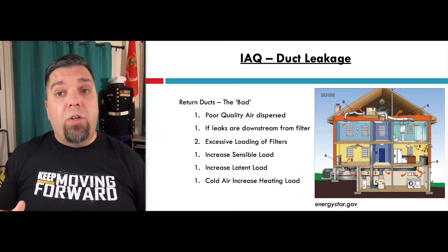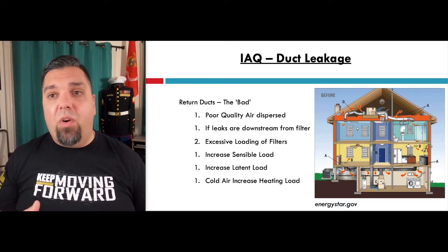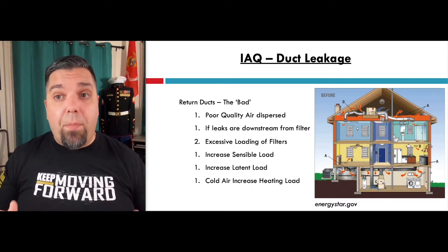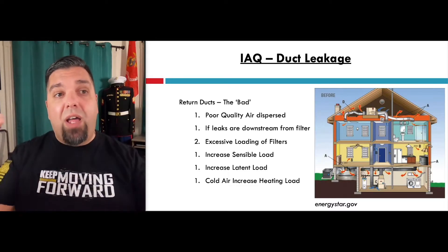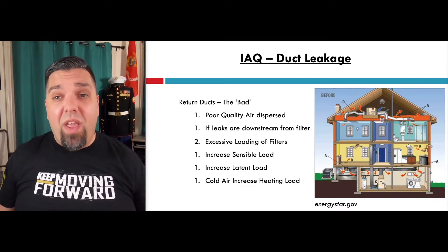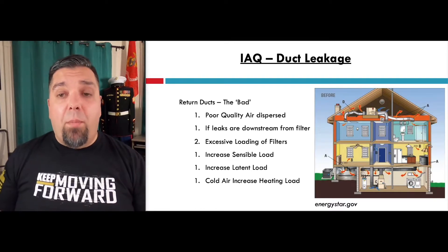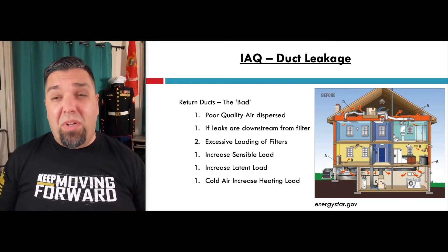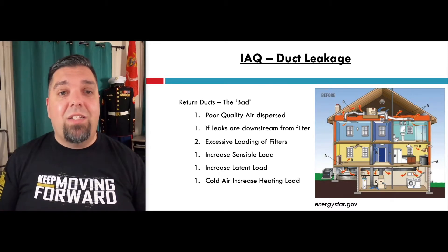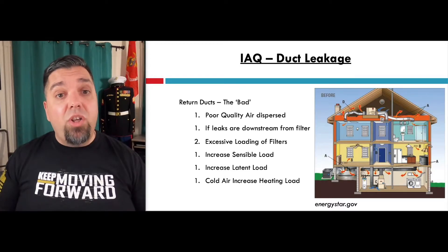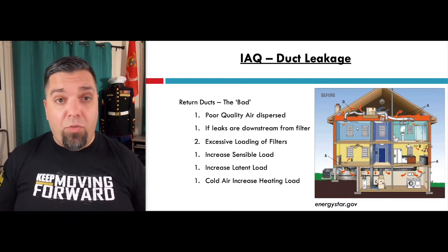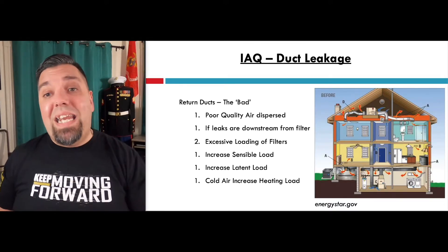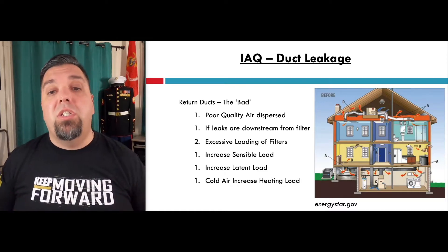Excessive filter loading will happen with all that leakage coming from a dusty attic or air from outside. In heavy pollen seasons you can easily pull pollen up into the attic — you can actually see it in the insulation where air was moving through it. All that stuff in a leaky return duct will load up that filter and you'll have to replace it very often. You're also going to increase the sensible and latent loads, and cold air from an unconditioned space increases the heating load in winter.